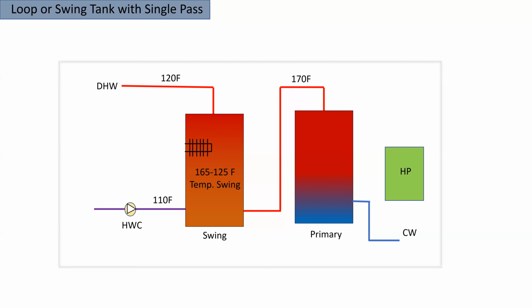One thing we've discovered with single-pass equipment is you cannot run warm return water through it without significantly degrading performance. This swing or loop tank concept allows you to reheat the circulation water without it touching the heat pump. The idea is you pulse really hot water through this swing tank, and there's enough temperature there to heat the recirc as well as supply the domestic hot water load.